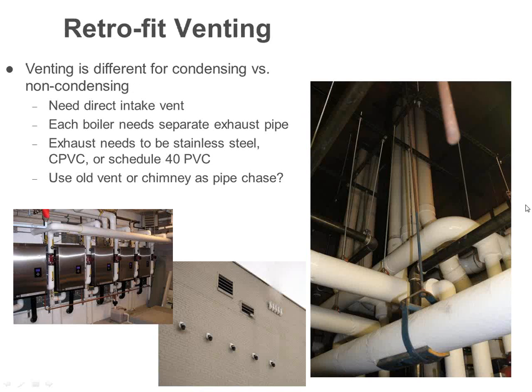One of the biggest things when you are dealing with condensing boilers is that venting is totally different. Okay? Since these boilers are running at very low temperatures, a lot of times we are using CPVC or Schedule 40 PVC. Some guys still use stainless, which is pretty pricey. But the venting is totally different because you've got to remember we are condensing. People say, well, my system's designed for 180. When does that 180 come up? 1% of the year. The rest of the time we can be running much cooler. That's why this venting is very critical.